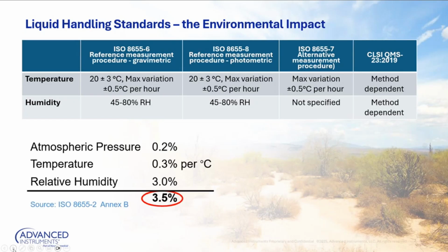Now here's what we know. ISO 8655 Part 2 has an annex in the back of it, and it shows you how much variation the environment could have on an air displacement pipette. You could potentially have a 3.5% impact on your volume strictly coming from the environment of your lab. If it's really, really dry in the laboratory, or if the temperature is fluctuating a lot, you could see that type of impact on your volume. And so that's definitely something that we want to consider for sure.